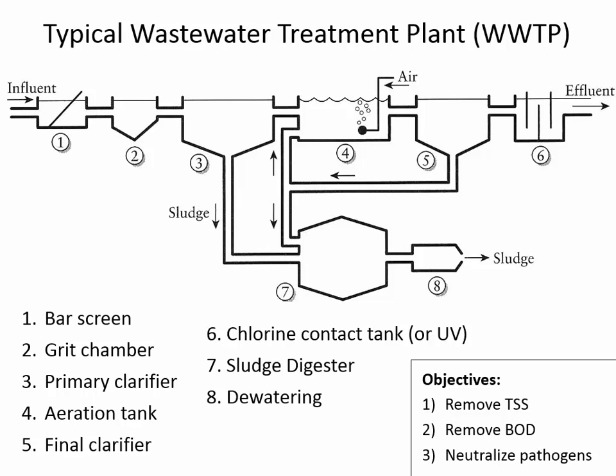The primary clarifier is before you get into the real magic of the wastewater treatment plant. In the primary clarifier, you're removing what will settle and what will float. You're maybe removing about 30% of the BOD through primary clarifiers. It's not removing the dissolved BOD, but the BOD that is still in floating and settling form. And I'll let your imagination do the work of what that is going to be. Like foam and grease will be removed off the top.